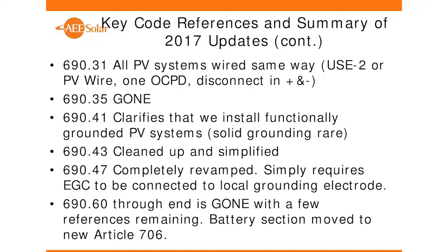Cleaned up and simplified 690.43 related to equipment grounding and equipment grounding conductors and bonding. Completely revamped 690.47, and this was one of the bigger ones. We talked earlier about this issue of grounding electrodes and things like that, how grounding electrodes have to be done in PV systems, or how they are done in all electrical systems. And there were just lots of words in there that were easy to misconstrue and get confused. We had DC grounding and AC ground, DC system grounding, AC system grounding, systems with both AC and DC, and it's like, I'm getting really confused here.